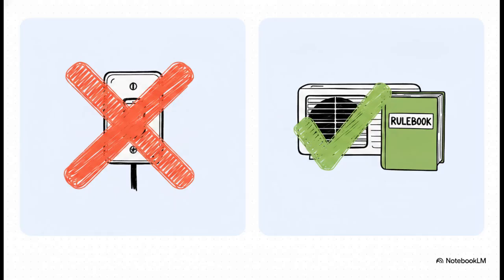Because of that hermetic motor, AC equipment leaves the general rules in the dust and follows NEC Article 440. This article is packed with highly specific rules for conductor sizing and overcurrent protection, tailor-made for refrigeration equipment. If you take away anything from this, it's this: treating an AC unit like a regular light switch is a guaranteed recipe for a failed inspection. You can't just pick the smallest wire that clears the load on paper, you have to follow Article 440.